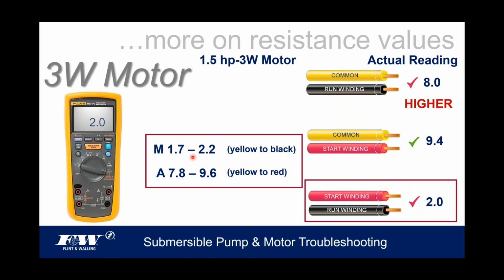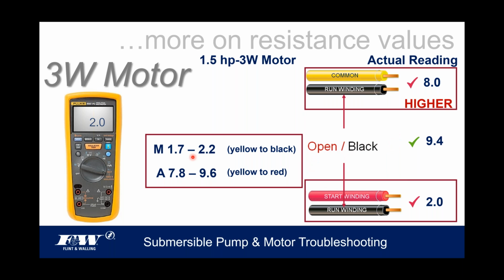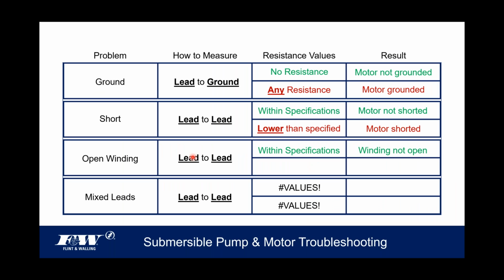And again, when we look at these two that fail, there's a fly in the ointment here, right? The yellow and the red worked good when they were together, throw that black run winding in, and it failed. So more than likely, that open winding is going to be in the run winding because, again, this is what my meter's telling me here. All right, almost through this. So this one's within specs. We're good. If it comes in higher, it's an open winding.